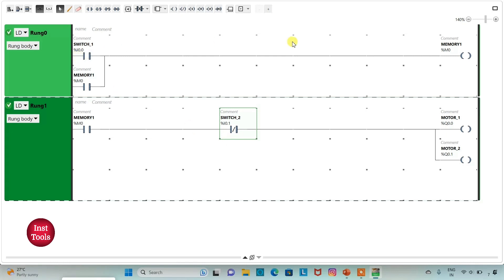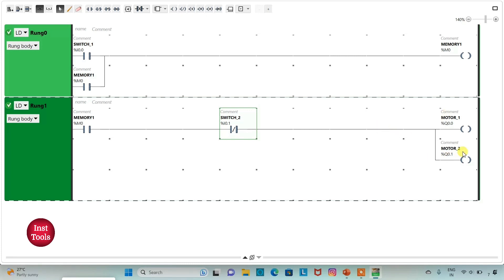So when SWITCH1 is on, MEMORY1 will be TRUE. When MEMORY1 is TRUE, current will flow through it. As SWITCH2 is a normally closed contact, current will also flow through it and MOTOR1 and MOTOR2 will be on. When we turn off SWITCH1, MEMORY1 still remains TRUE, so current continues to flow and MOTOR1 and MOTOR2 remain on. When we turn on SWITCH2, since it is a normally closed contact, turning it on stops current flow, and as a result MOTOR1 and MOTOR2 will be off. So we have implemented latching and used a normally closed contact.